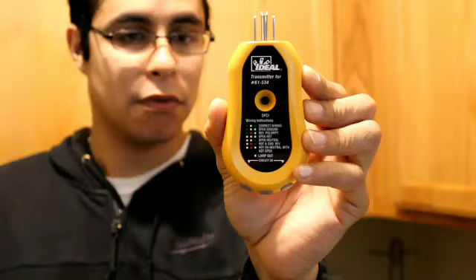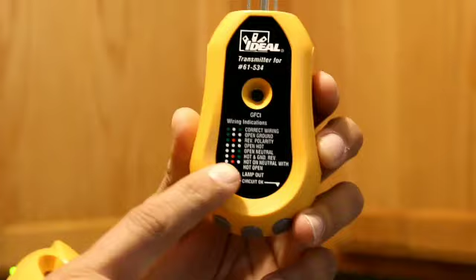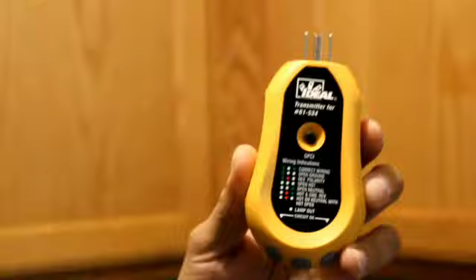Now let me show you how you can use this as a GFCI tester. First, you have the testing button here that says GFCI. Keep in mind this is for 3-wire outlets only, 120 volts AC. You also have a legend that tells you correct wiring, open ground, reverse polarity, open hot, open neutral, hot and ground reverse, hot on neutral with hot open, and lamp out.